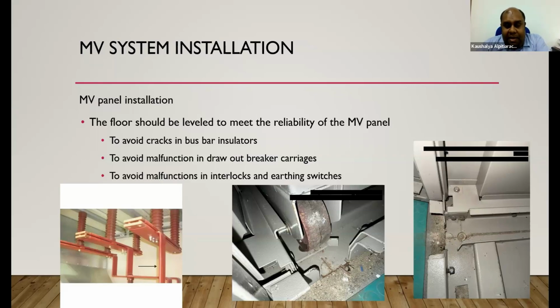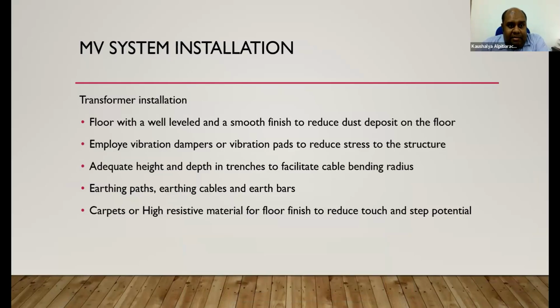Sometimes you will find issues related to interlocks and earthing switches as well, especially if that's an AIS system, because longer rods will have to be used as the panel construction is bigger. In those cases, some torsion and unwanted stress will apply on those areas. Transformer installation, same thing. The floor should be level and so on. We need carpets, earthing paths, earthing cables, and earthing bars to be there at the right places, at the right distances.